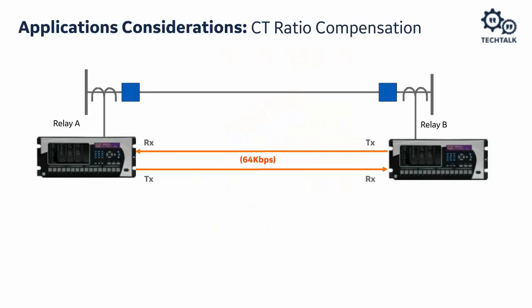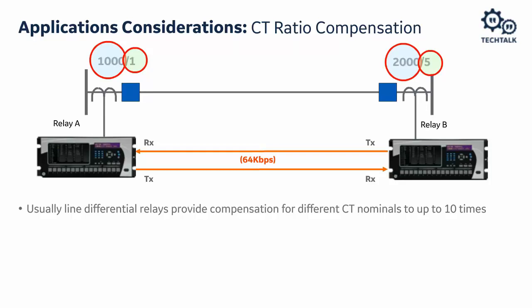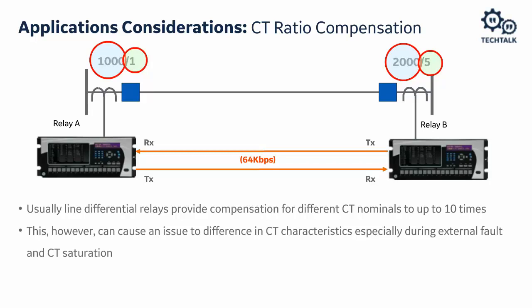One application consideration is different CT ratios at each substation, which can occur when different utilities have different standards. Today line current differential relays can tolerate up to 10 times CT ratio difference, depending on the relay. However, when there is a very large CT ratio difference, issues can arise during external faults because CT characteristics differ: one CT may saturate more than another, or one saturates while the other does not.